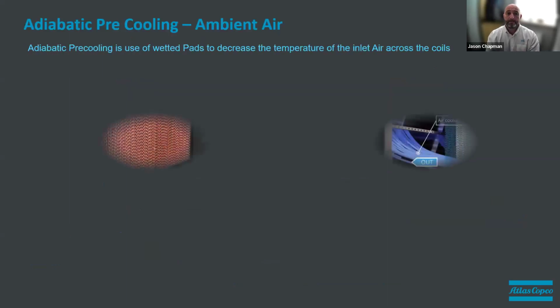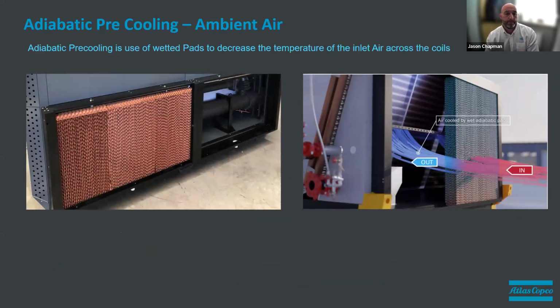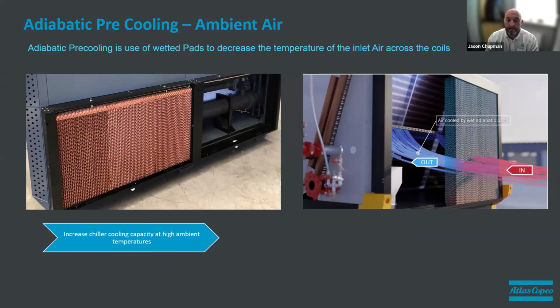Adiabatic pre-cooling. So, as I said before, what is this? A bit of a magnified picture there of the actual adiabatic pads. And how does this work? As we said, it increases the chiller cooling capacity at high ambient temperatures. So when we do have the hot months or the hot couple of weeks potentially that we only get in the UK, we can saturate these pads with normal water. There's no chemicals, no glycol, or anything in it. It's just normal city water as such. So it just runs through.